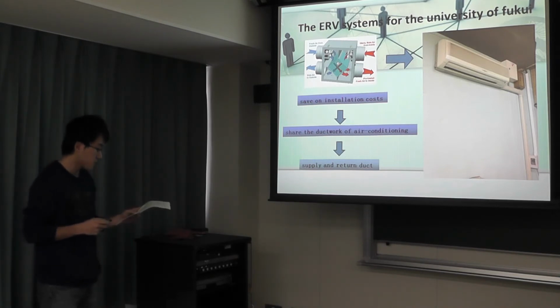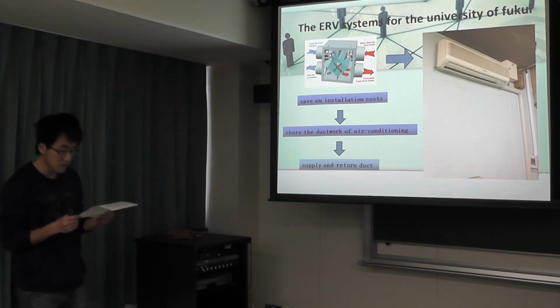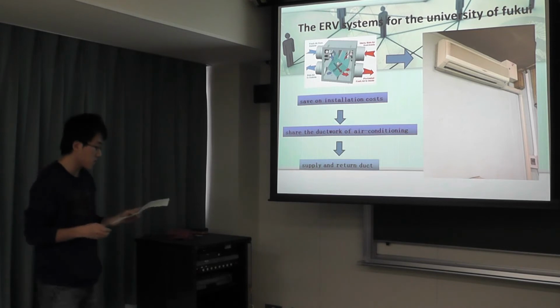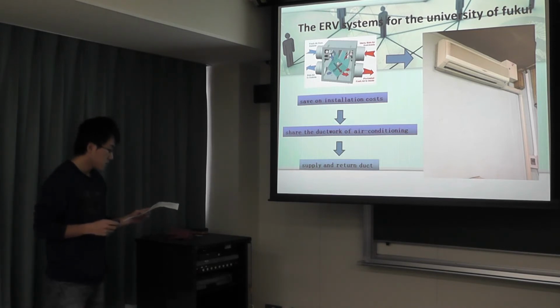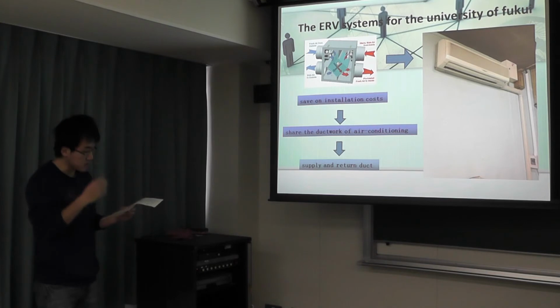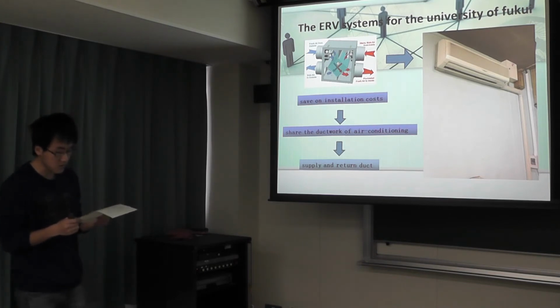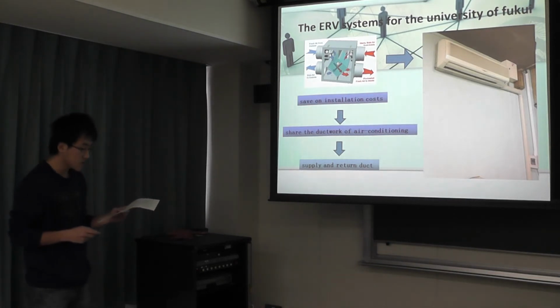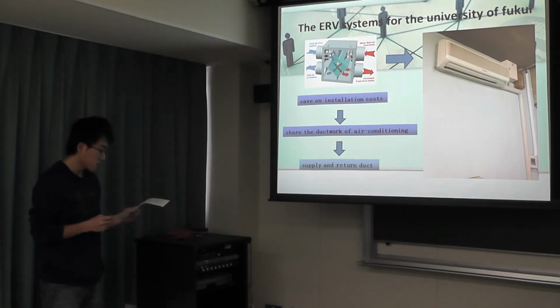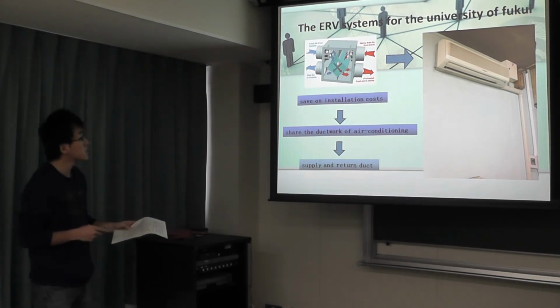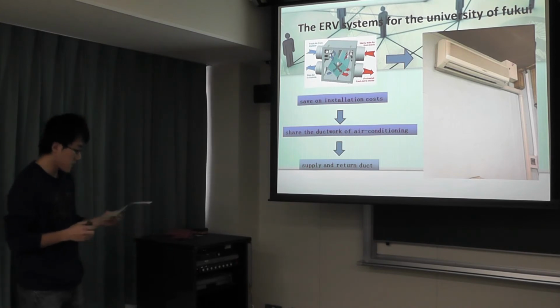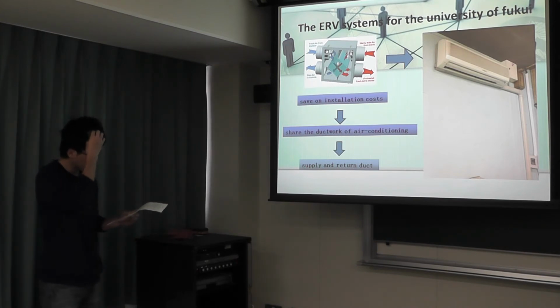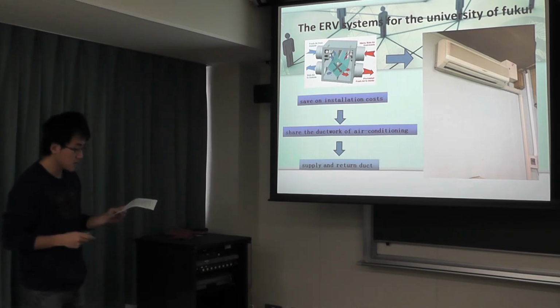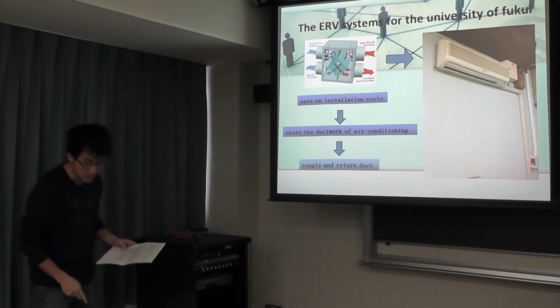I want to have a supply and return duct for each room and for each common living area. Duct runs should be as short and as straight as possible. The correct size duct is necessary to minimize the pressure drops in the system and thus improve performance.